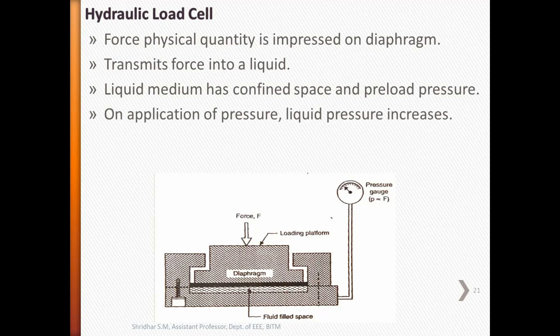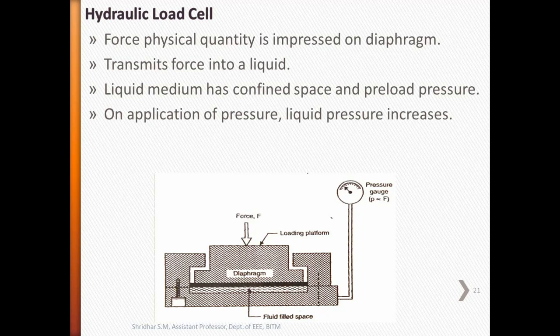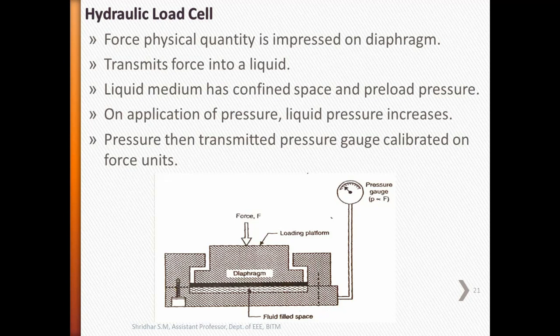On the application of the force, the liquid pressure increases and equals the force magnitude. Then the pressure is transmitted to a pressure gauge which is calibrated on force units. These cells have been used to measure loads up to 25 MN with an accuracy of 0.1% of full scale and resolution is about 0.02%.